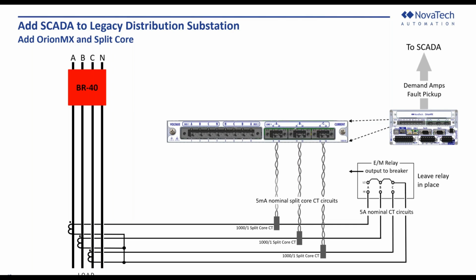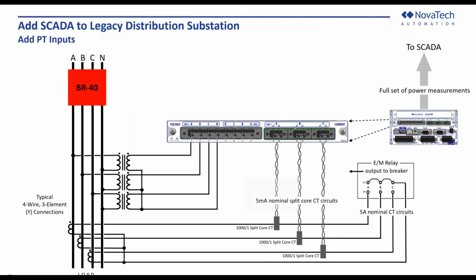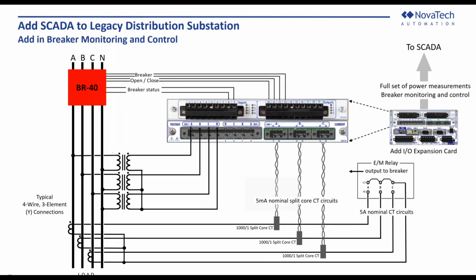So what would that give you? It would give you demand amps, fault pickup, plus anything related to current. I think demand amps would be valuable for your planners to see how your loading was changing on that line over time during holidays. Maybe look at transformer loading, that kind of thing. So the next thing you'd consider is adding in some of your voltages. So this is a typical 4-wire, 3-element Y-connected system. So those 3 voltages come in and they actually land just as shown in the diagram. And so now you have a full set of power measurements. You have watts, vars, things like that, energy values, all kinds of things. So this gives you the full set of power. And then the next logical step would be to add in some discrete I/O so you could check for breaker status and also send down breaker open and close.